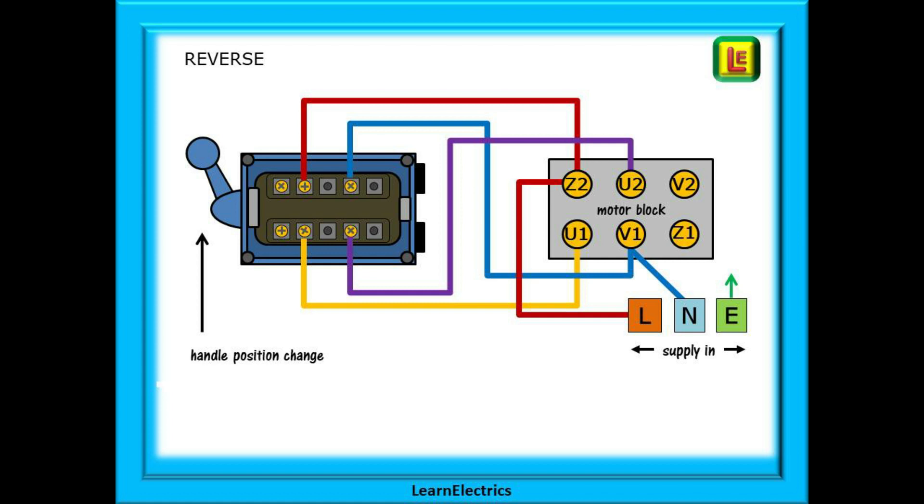Let us put the motor into reverse now. Again the only visual change is the selector arm but what has happened inside the switch? The dotted lines show the internal crossover connections. Phase is now connected to U2 and neutral to U1. The motor will turn in the reverse direction. And that is all there is to it.